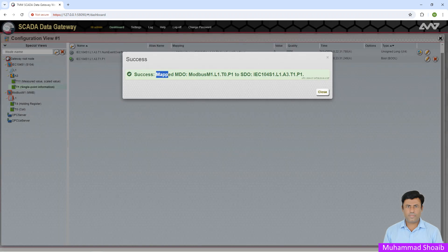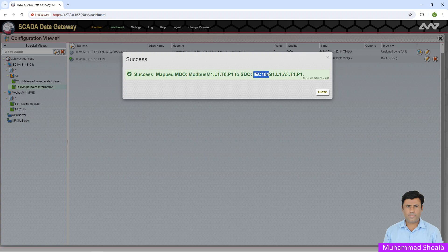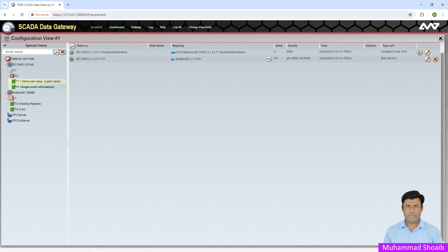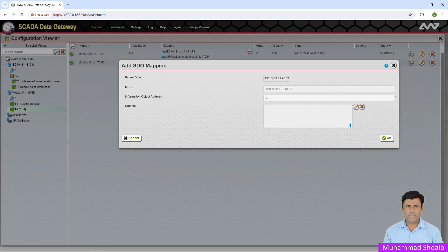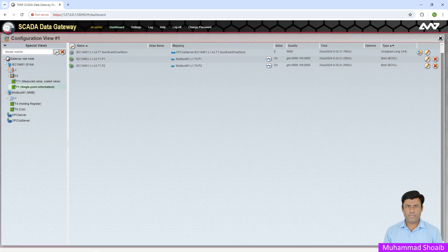What we actually did: we performed the mapping between the master data object and the slave data object. The master data object corresponds to the Modbus protocol side and the slave data object corresponds to the IEC 104 tags. Click Close. Similarly, we'll go for the second tag — select the coil, drag and drop it over the T1 Single Point Information Object, and press OK. Here also we successfully completed the mapping. Press Close.